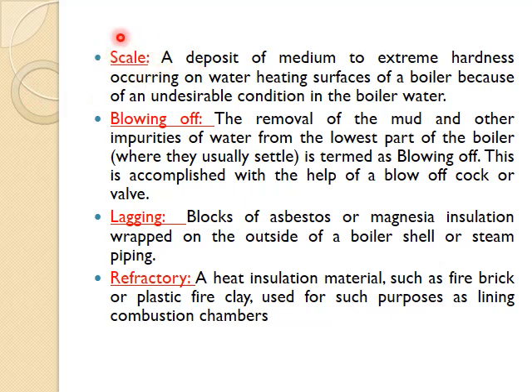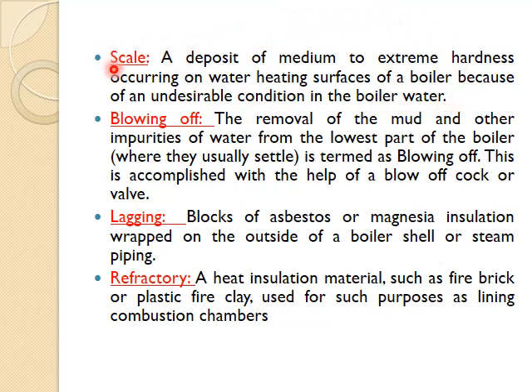Scale: a deposit of medium to extreme hardness occurring on the water heating surface of the boiler because of undesirable conditions in the boiler water. If the boiler water contains dissolved or undesirable particles, those particles will deposit on the tubes of the boiler — that deposition is called scale formation.